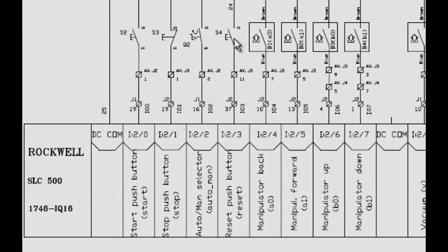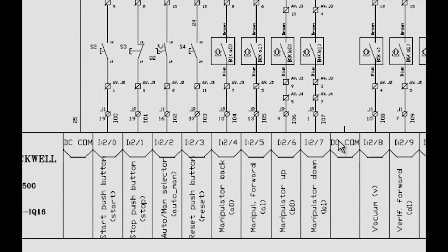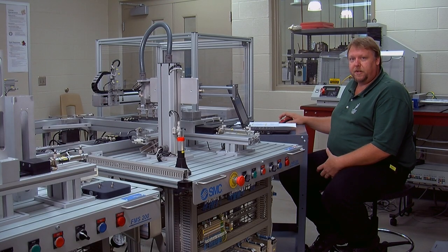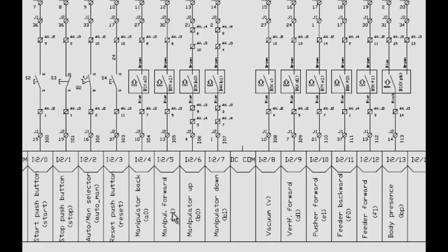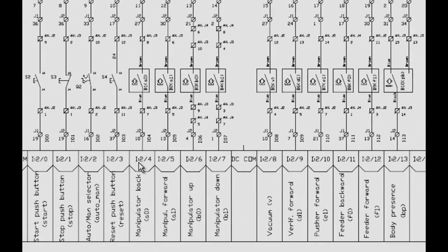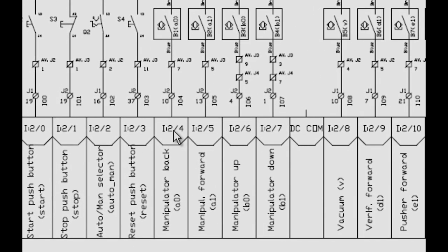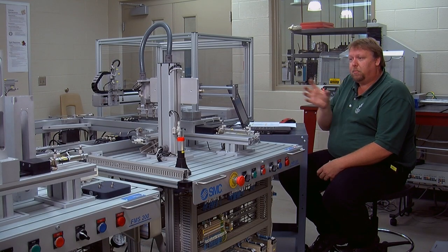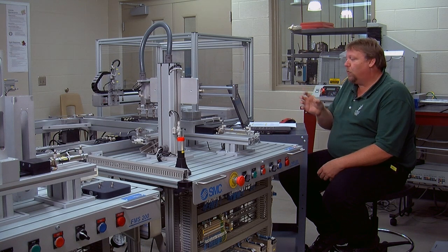Next one is an auto/manual switch, and we've got a reset push button. All of the rest of these are indicators attached to the cylinders — it's a reed switch. Each cylinder inside has a magnet, and when that magnet passes over it, it allows that sensor to be triggered. So if we look at the very first one, I:2/4, it says manipulator back, referring to the cylinder on the actual station that places it backwards and forwards.